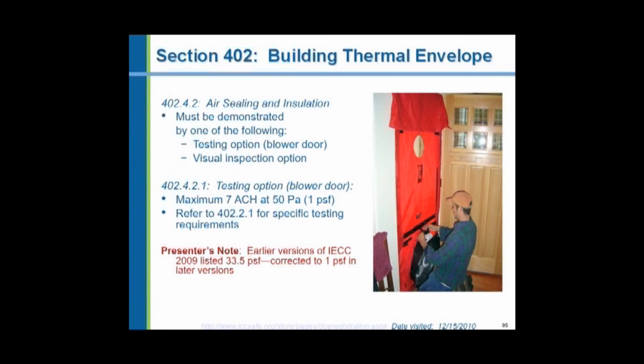The gentleman has installed the blower door, and he's now putting in the blower itself in a circular opening in the bottom portion of the door. And this is an exhaust fan, variable speed, with air measuring devices built into it, little probes. And you can adjust the speed of the blower, and you can read out the air volume that's being exhausted through that blower in cubic feet per minute. And the new Energy Code says that you shall have a maximum of 7 air changes per hour in that house. But it's at a pressure, or rather a suction on the house, of 1 pound per square foot.